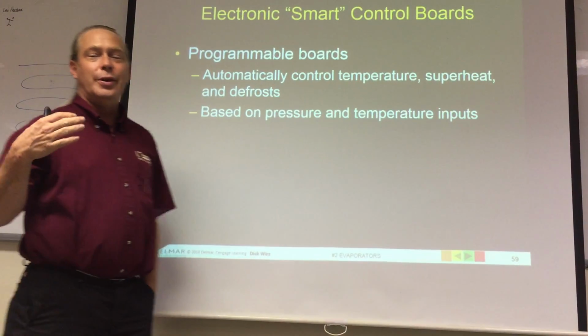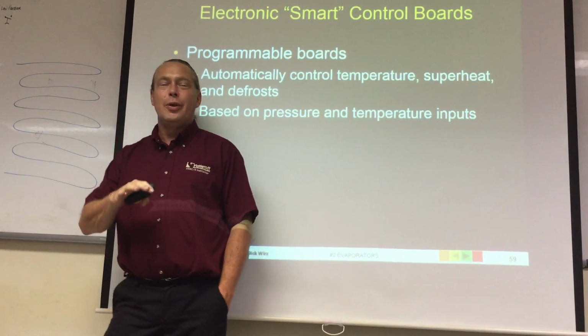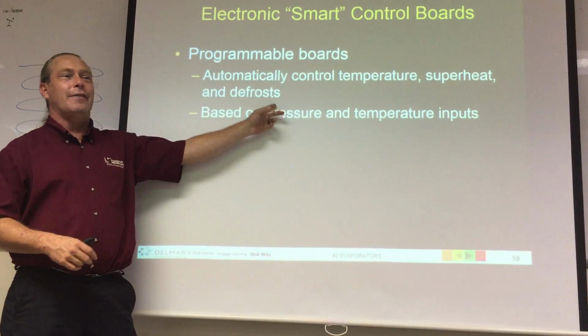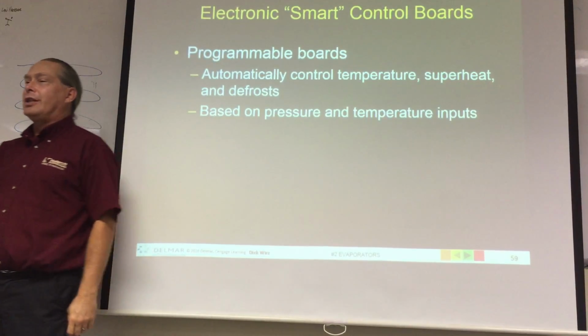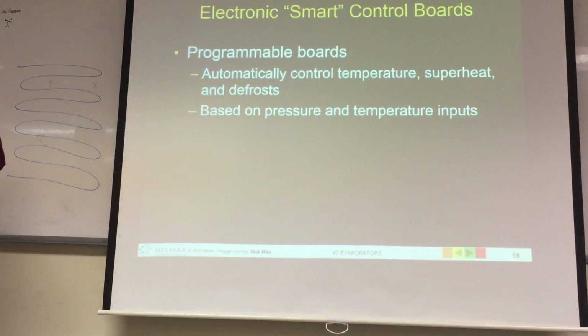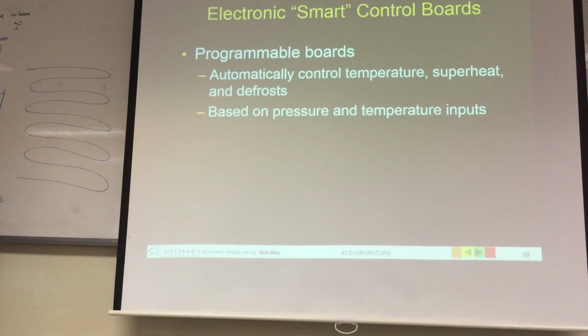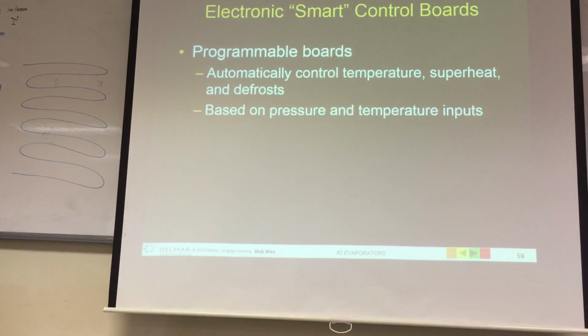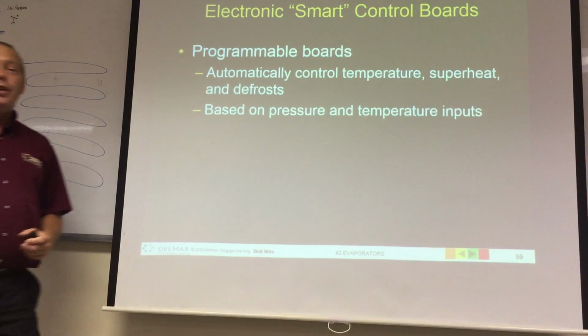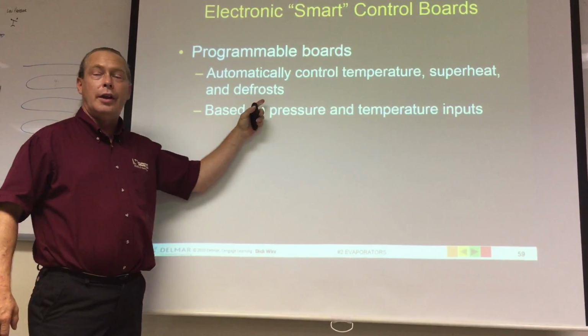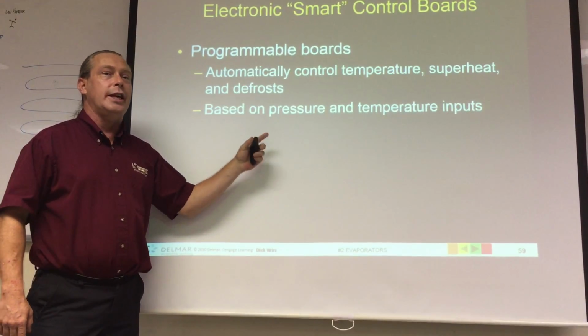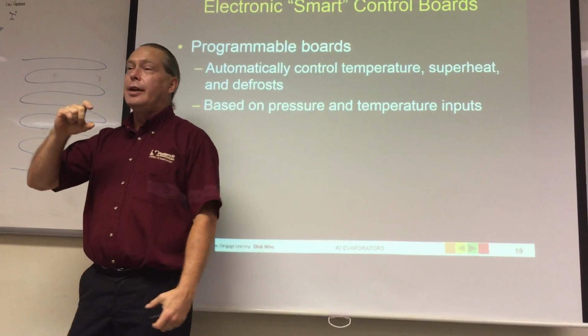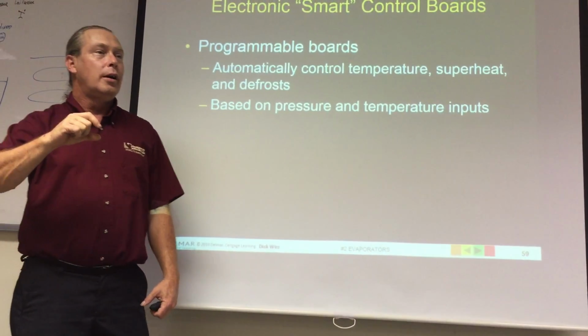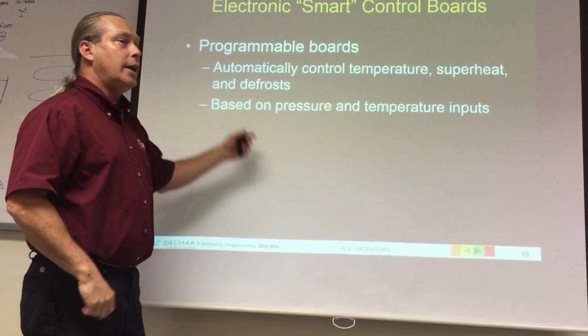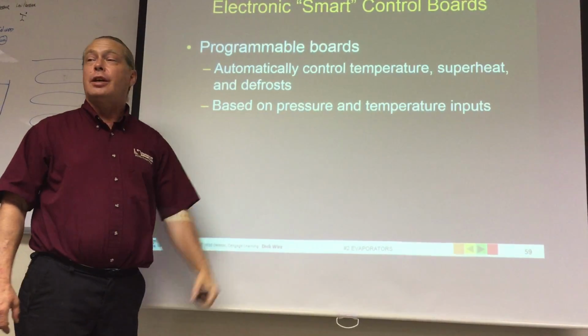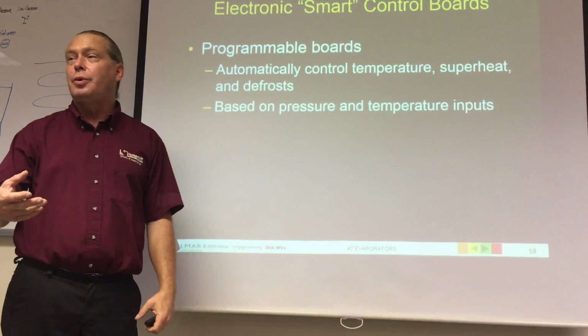Now, you guys, we're in review, so I'm going through this a little bit faster, but is any of this bringing something to mind that we discussed last week? External TXVs? Automatic one. The electronic TXV. Yeah, electronic TXV. Yes, what's that? You can have one board that does all this. It controls the TXV. It uses the TXV as a liquid line solenoid to pump down when it wants to. It controls the superheat, maybe it has some sort of input on subcool as well.